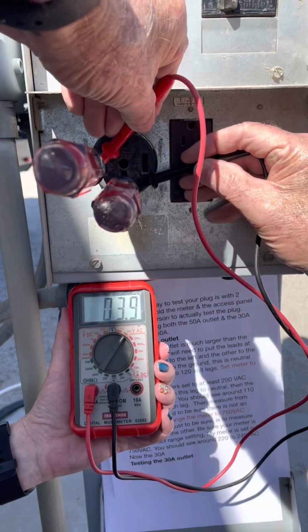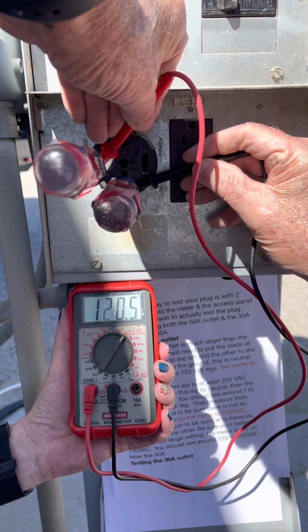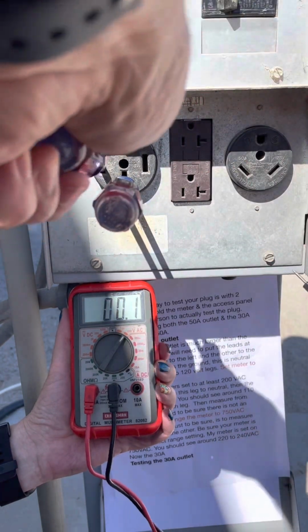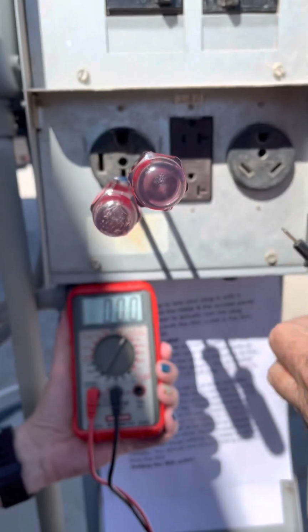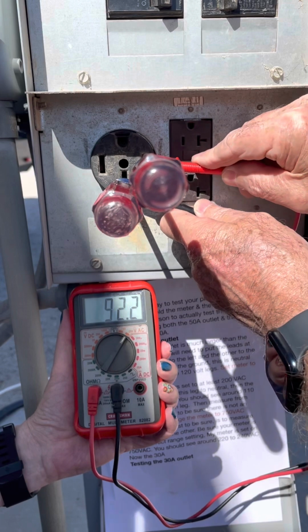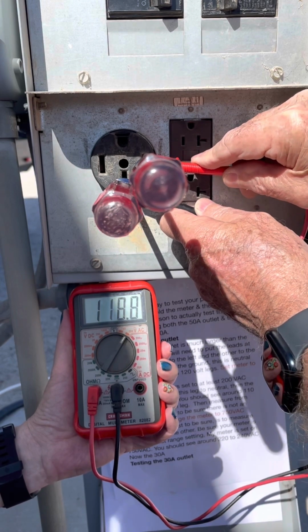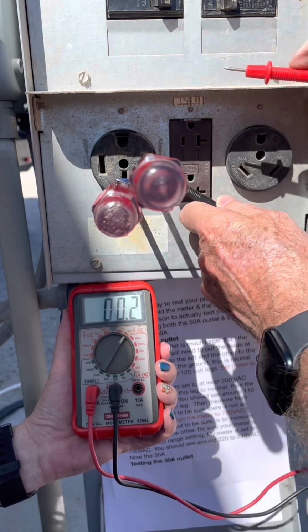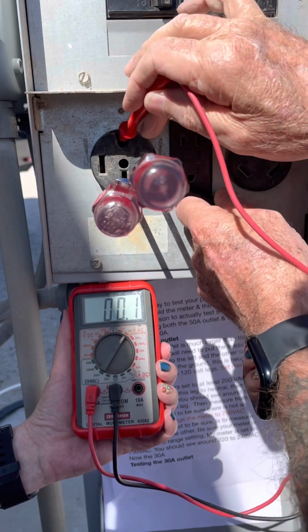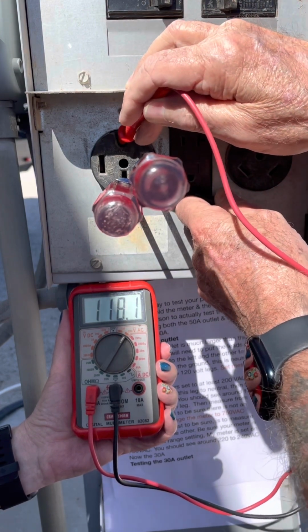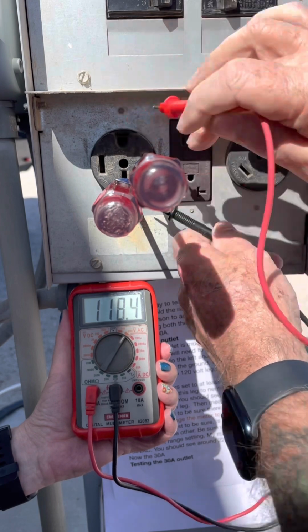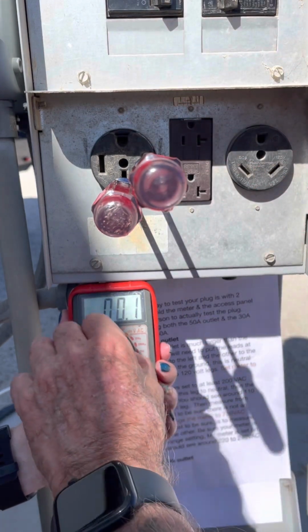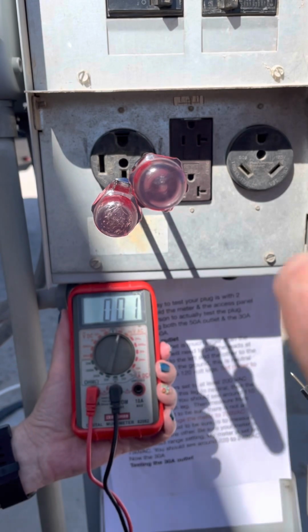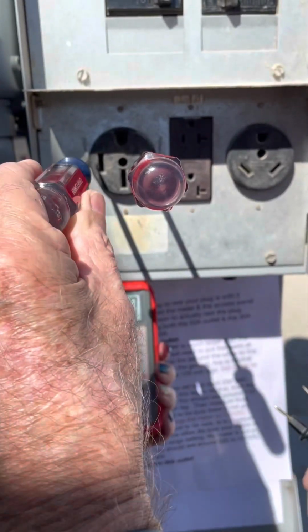And we should see somewhere around 120 volts. And we're going to measure from the other leg to neutral. Again, 120 volts. We also want to confirm that we don't have an open ground, and we will test from a leg to ground. The last test we want to make is to check from leg to leg. This is kind of a double check to make sure everything's working correctly.